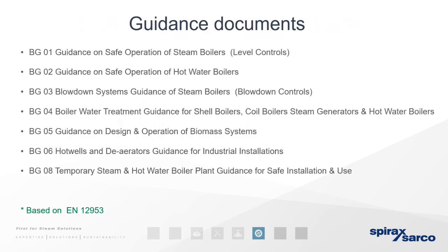So again, more guidance documents. These are things that aren't necessarily law, but to follow them means that you're in compliance. So you have BG01, which is guidance for safe operation of steam boilers. BG02, guidance for safe operation of hot water boilers. BG03, which is blowdown systems. BG04, which is boiler water treatment guidance. BG05, guidance on design and operation of biomass boilers. Again, in East Africa, that may be quite handy. BG06, hot wells and deaerator guidance.